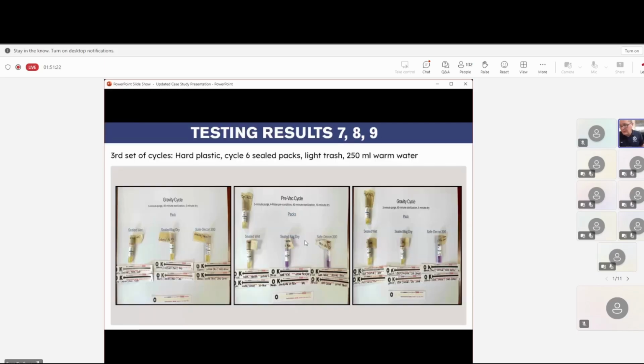One more thing on cycles 7, 8, and 9 I want you to see real quick: this was a gravity cycle on cycle 7 with very tight packs. This is a gravity 40-minute cycle with a 3-minute purge, and I wanted to push it to the absolute maximum using that 40-minute cycle, even though it only takes 15 minutes to kill a spore.